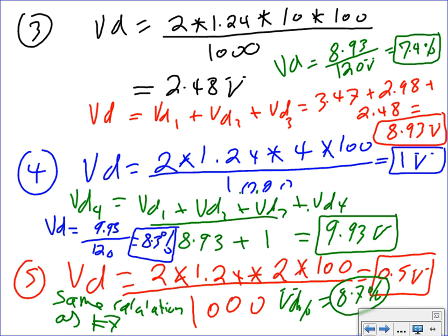Expensive is, do you need your system to work efficiently? But if we're to redo this system as an exercise, then I would start with number 8, number 6 conductor. I would use number 6 right away, because the voltage drop looks like number 6. Put number 6 and do the same calculation.